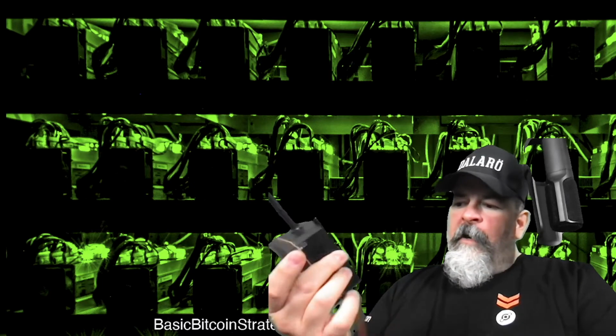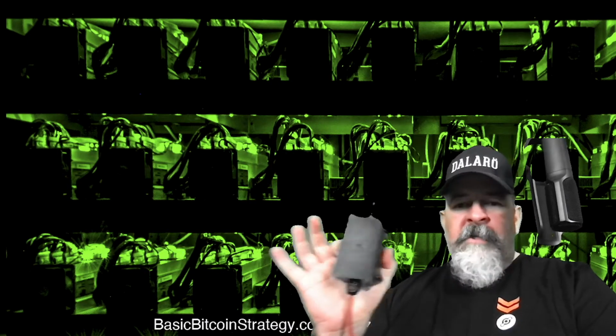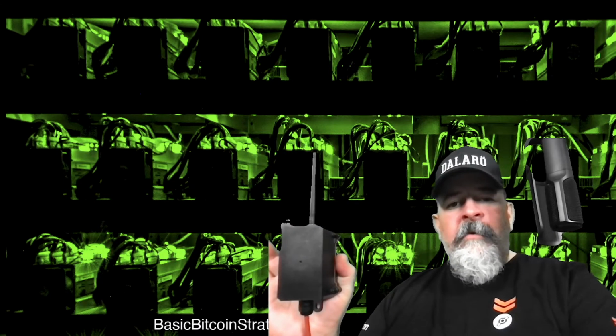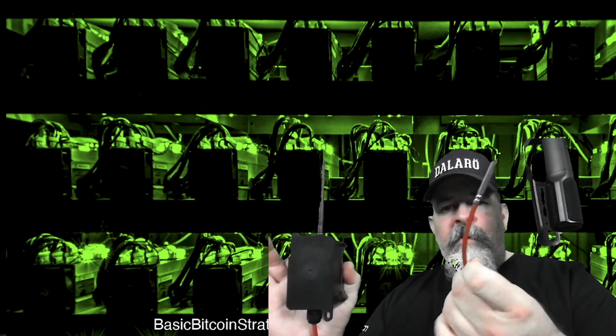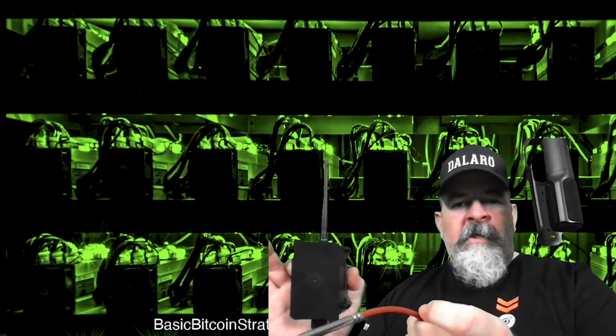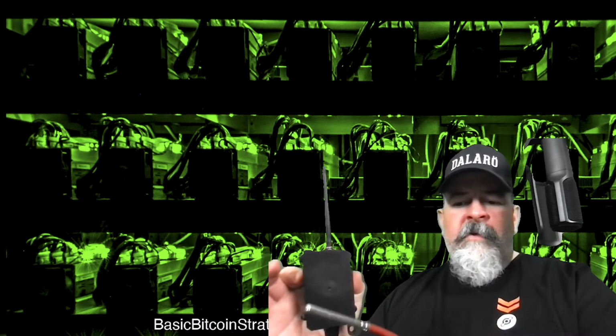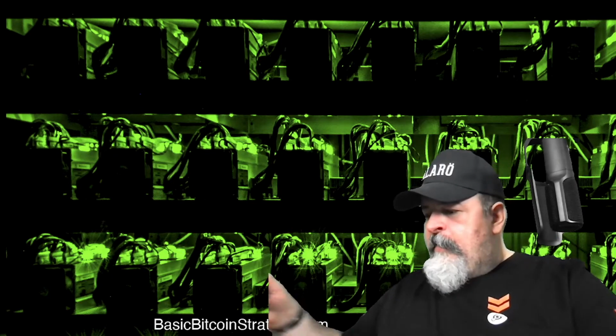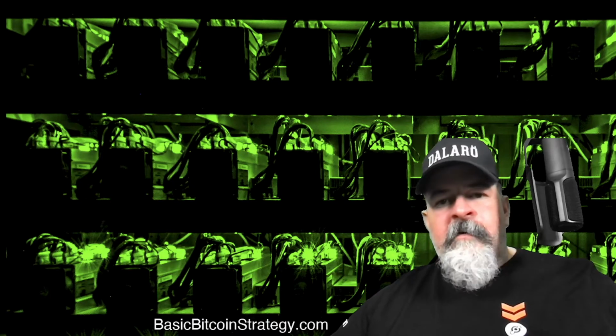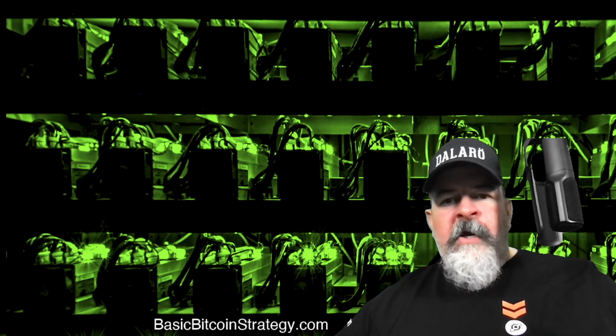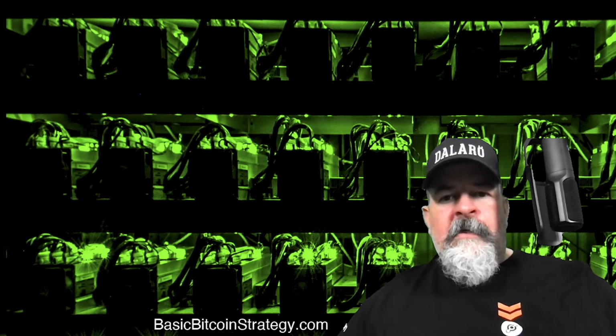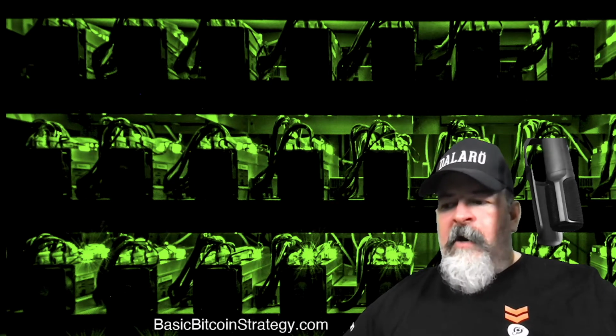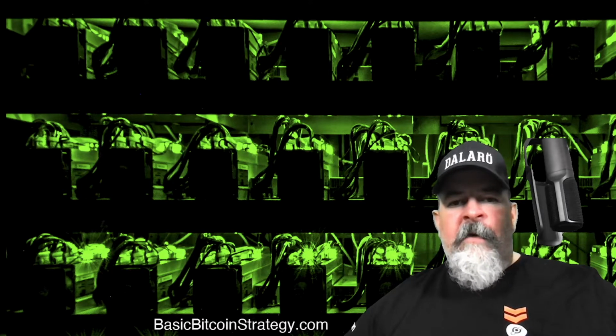So I'm simply going to attach this to a dry cooler. I'm going to take this probe and place it between the insulation and the pipe so I can get water temperature off of the pipe. That way, if I have 110 degree water coming out of my dry cooler but it's 80 degrees outside, I know I have a heat exchange problem and I need to get my HVAC company out before I start seeing failures in our data closet.